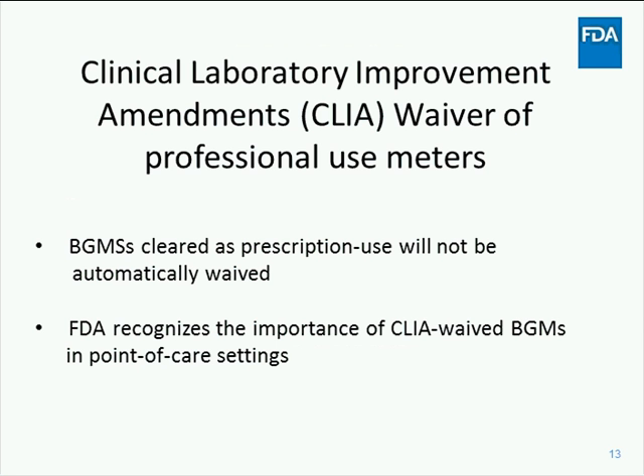FDA's clearance of 510K submissions for SMBG devices intended for over-the-counter home use allows for automatic CLIA waive categorization. Now, as discussed in the previous slides, most blood glucose meters on the market today, even those that are used for healthcare professionals, were previously submitted to FDA with claims for over-the-counter use by lay users and were therefore given CLIA waived categorization. Clearance of BGMS systems as prescription use devices intended for point-of-care use in professional healthcare settings as described in this guidance means that they will not be automatically CLIA waived.